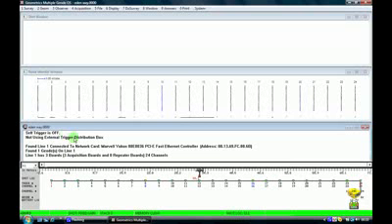The next window down is what we call the log file. The geode creates a file of everything that you do during the day for its own internal purposes, but also for you for a useful quality control function at the end of the day, so you can tell what you did and when, what parameters you used to record the data, where the shots were recorded, etc., etc.